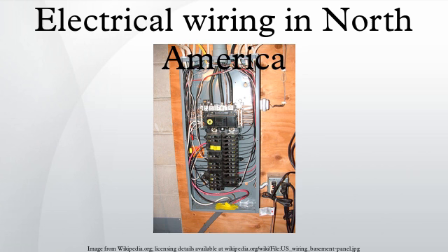XHHW-2 insulation, which is similar to XHHW, is suitable for use in dry or wet locations up to 90 degrees Celsius. THWN stands for thermoplastic heat and water resistant nylon coated. THWN is a designation for a specific insulation material, temperature rating, and condition of use for electrical wire and cable.